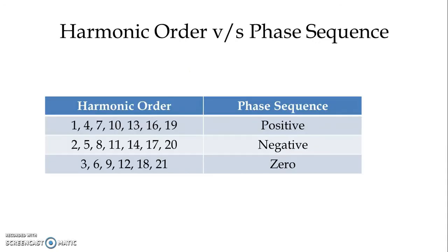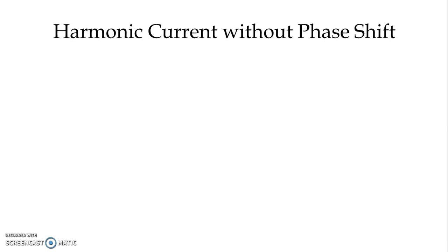If we check harmonic orders versus their phase sequence: harmonics 1st, 4th, 7th, 10th, 13th, 16th, 19th are all positive sequence harmonics. Harmonics 2nd, 5th, 8th, 11th, 14th, 17th, 20th are negative sequence harmonics. Third and multiples of three — the triplen harmonics — are zero sequence harmonics: 3rd, 6th, 9th, 12th, 18th, 21st, etc. The expressions considered so far for harmonics have zero phase shift with respect to the fundamental.